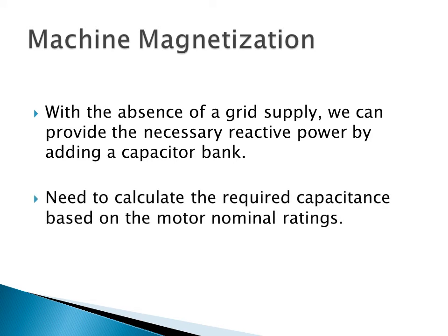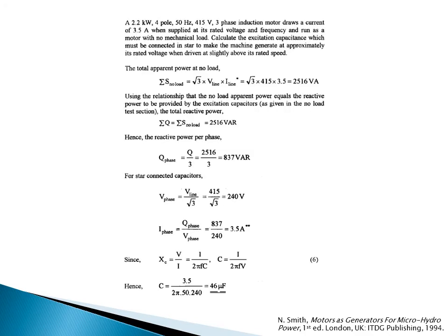We will, however, need to calculate the required capacitance based on the motor's ratings and the anticipated load. In the example here, we can see that we're presented with a 4-pole, 2.2 kW, 50 Hz, 415 V, 3-phase motor, which draws a current of 3.5 A at its rated parameters. Without going through the calculations, you can see how we calculate the required reactance, and therefore the required capacitance for this particular motor setup to be used as a generator.